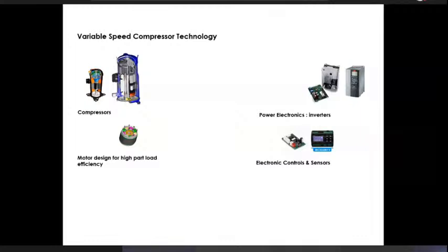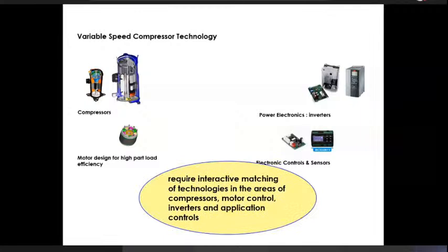What happens when the load goes low and the compressor speed goes low is that the expansion valve needs to change. It needs to allow less refrigerant to flow for the same pressure drop or for a reduced pressure drop. At the same time, we want to be sure that the compressor operating envelope, which means the combination of pressures and temperatures on the suction and the discharge, is not exceeded. The current being drawn by the motor must not go above what it is rated for. All of this knowledge has to be built into a software algorithm so that we ensure reliable operation throughout the life of this product.